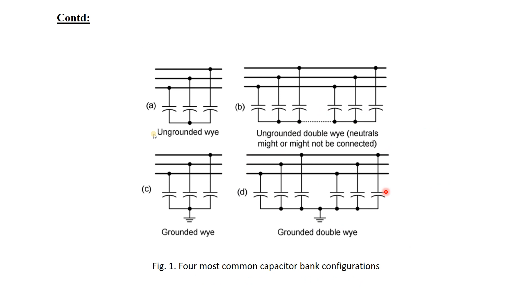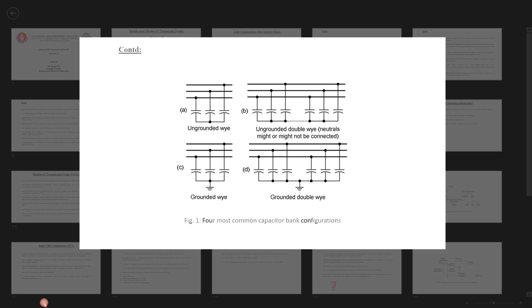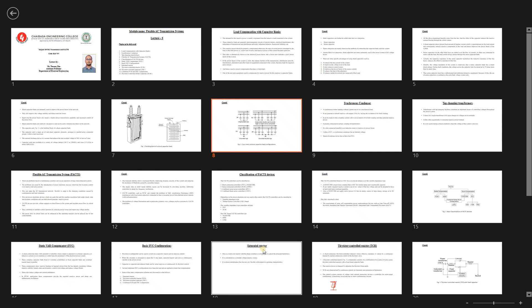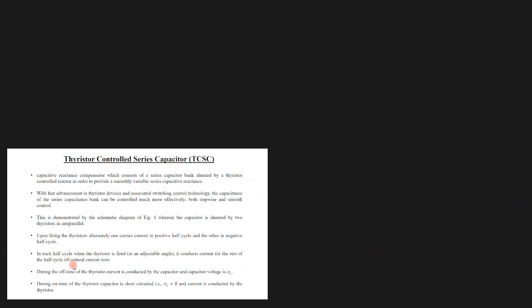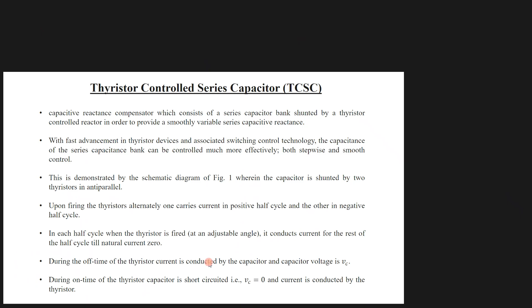So in TCSC also, this entire capacitor bank is connected in the system, but it is connected in series, not in shunt. You can see this particular capacitor is one capacitor bank as a whole. This bank is connected in series with the line, but it is totally controlled with the help of a thyristor and a reactor connected to it, because the reactor is required for limiting the current.